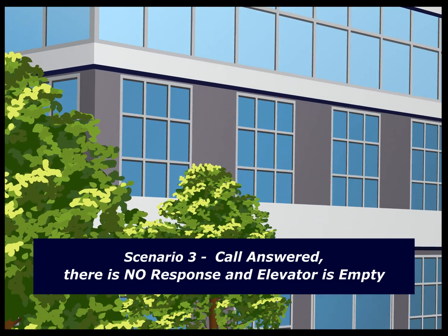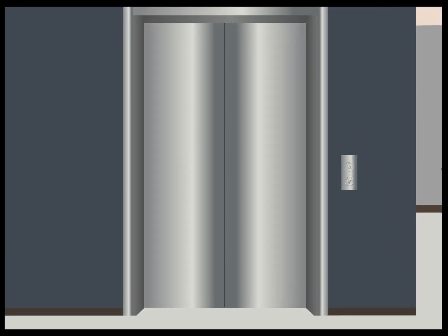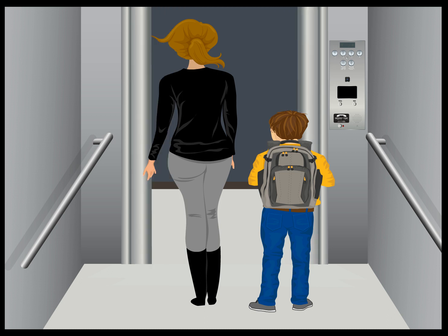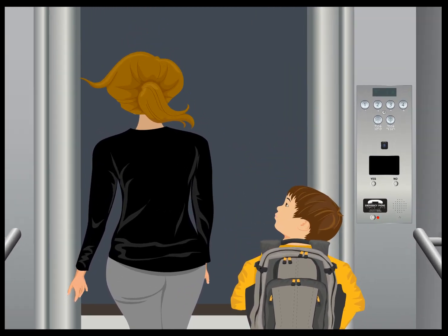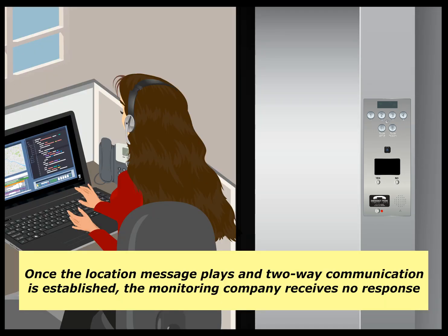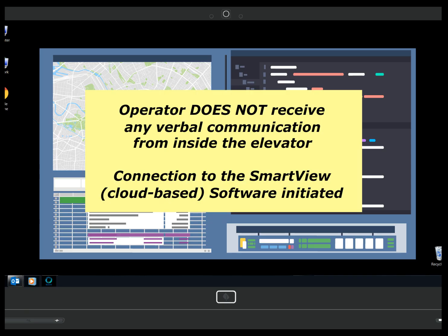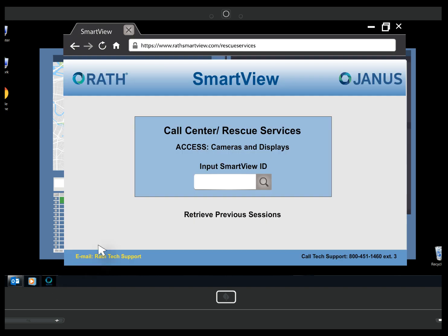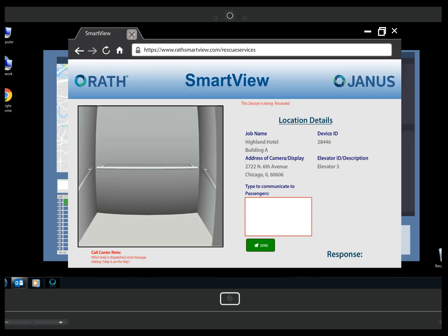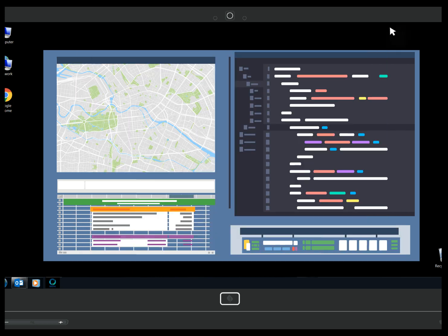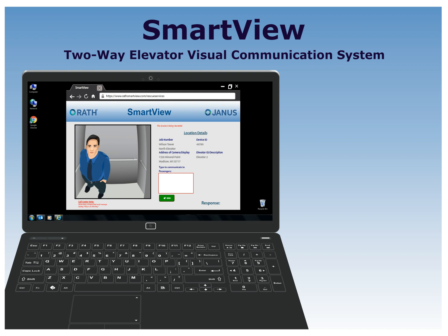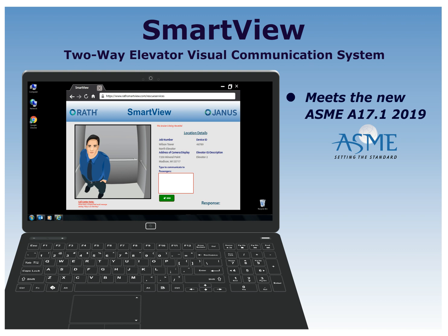Scenario number three: the call is answered, there is no response, and the elevator is empty. Many elevator phone activations are accidental. In this scenario, a child is playing and pushes the phone button as they are leaving. A call comes into the monitoring company. Once the location message plays and two-way communication is established, there is no response. The link to the SmartView software is opened, the unique ID is entered, and the camera enables — the monitoring company can see there are no occupants in the elevator. The call is then canceled, saving money from needless dispatches.